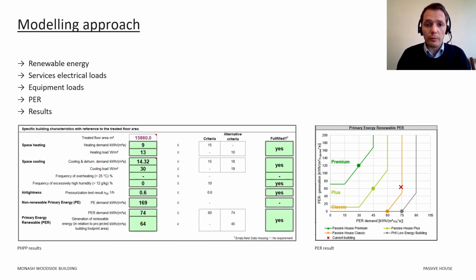Even so, we're right on the border of the allowable PER demand, which points out that the electrical loads from the mechanical ventilation units of heat recovery, the VRF plant, the domestic hot water plant, and equipment loads need to be kept to a minimum if you want to achieve the stringent energy benchmarks.